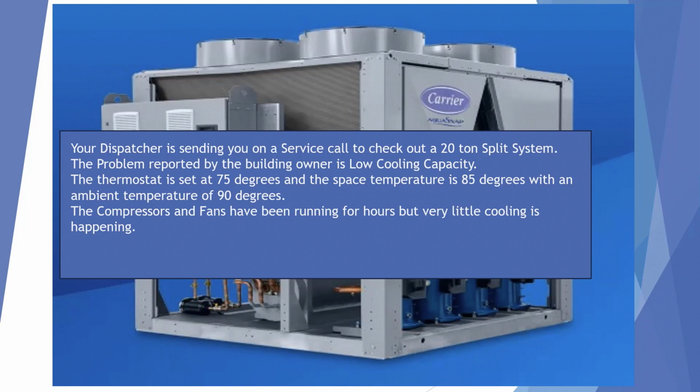The thermostat is set at 75 degrees and the space temperature is 85 degrees with an ambient temperature of 90 degrees. The compressors and fan have been running for hours, but very little cooling is happening.